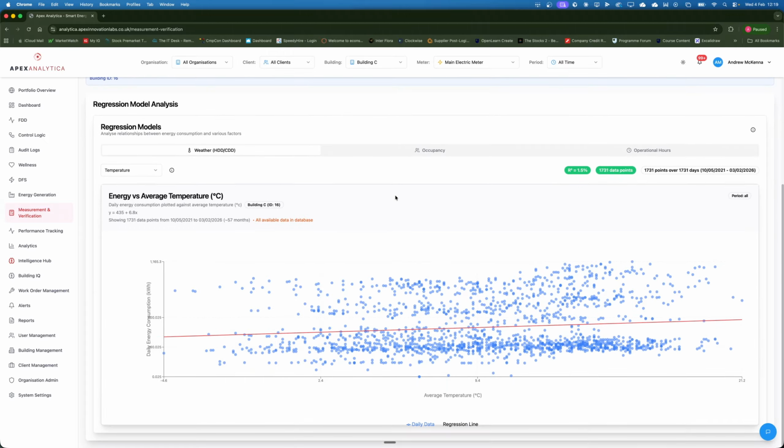We can also look at models. So you can see here, this is all time in terms of the correlation between heating and cooling degree days against temperature. So you can see this building particularly doesn't measure well in terms of efficiency. So you can see, like here, it's minus 4.1 degrees and we are using 871 kilowatts. So you'd absolutely perceive this as a heating season, but still using around 871 kilowatts. As in over here, when it's like 19.6 degrees, we're still using 990 kilowatts. So what this tells us is seasonal variability doesn't really factor in. The consumption in the winter is just as high as the consumption in the summer.